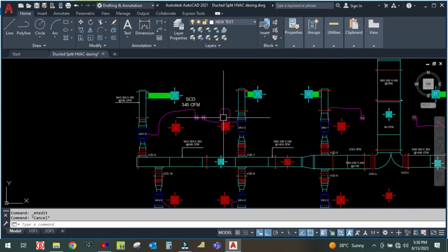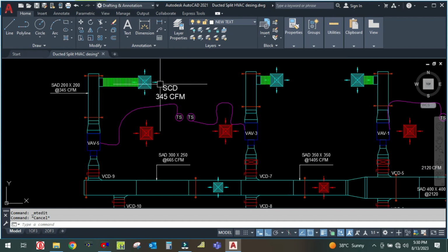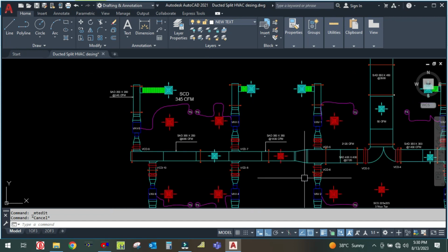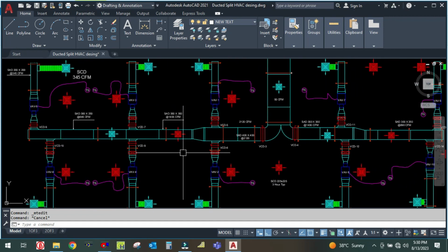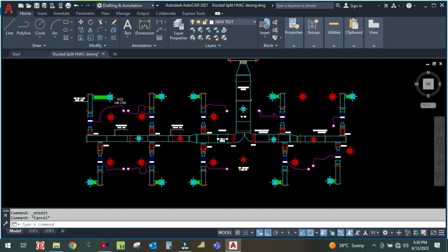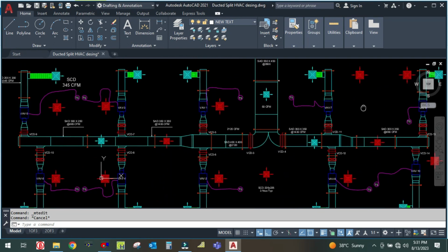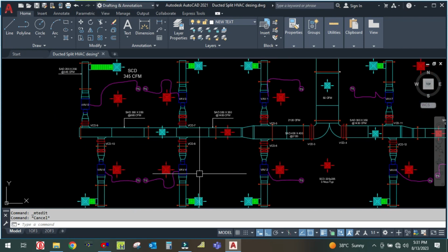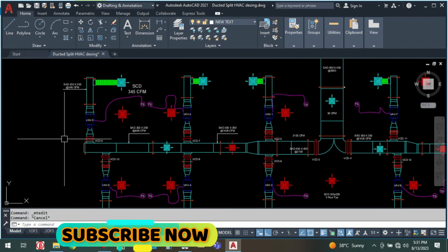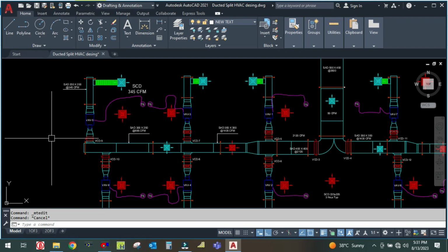In each branch the flow rate is 345 CFM only, so each branch duct size will be 200 by 200, and this side also will be 200 by 200. This is how we design the duct size, the main duct and branch duct, with the equal friction method.